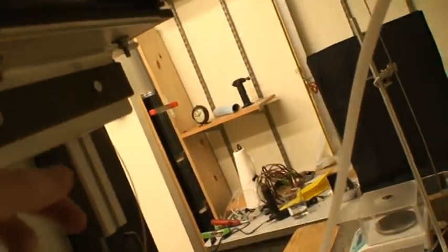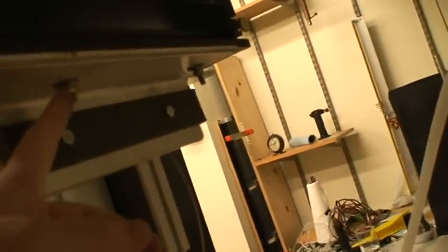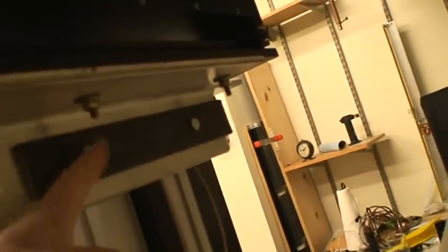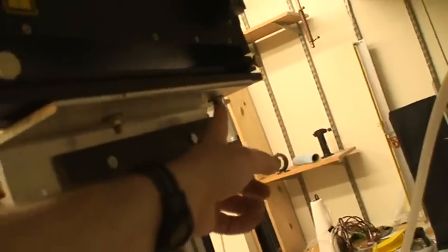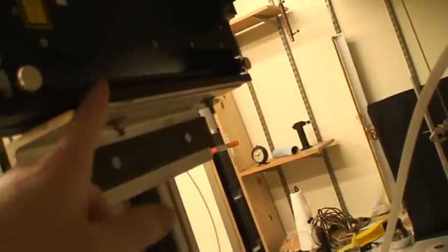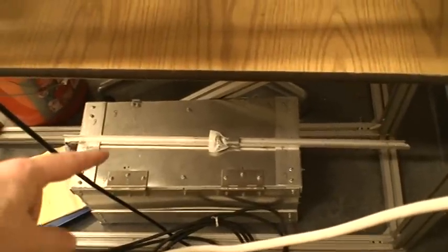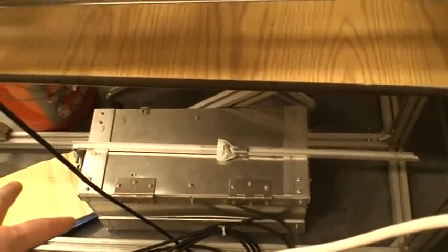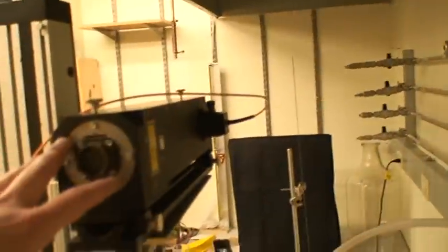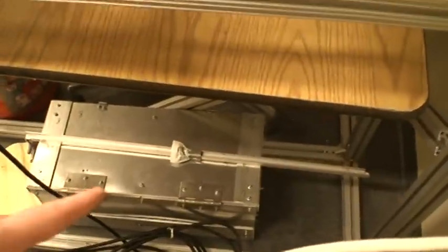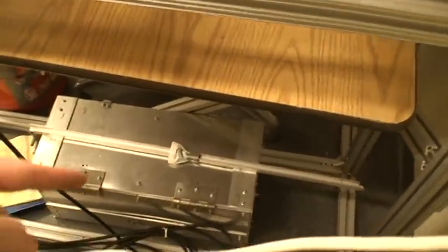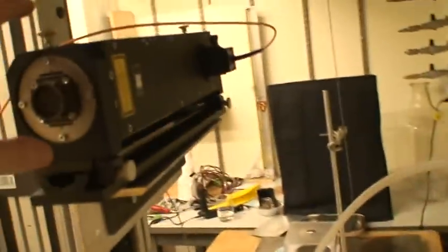The slide is connected to this mounting bracket with two bolts, so you can take the mounting bracket itself off. If you disconnect these two bolts, you can take this off and it will also fit inside this silver box, this aluminum box. You can put the whole laser assembly inside of this box, and the box was built to protect the laser assembly from any radiant and incident radiant heat flux from a fire.